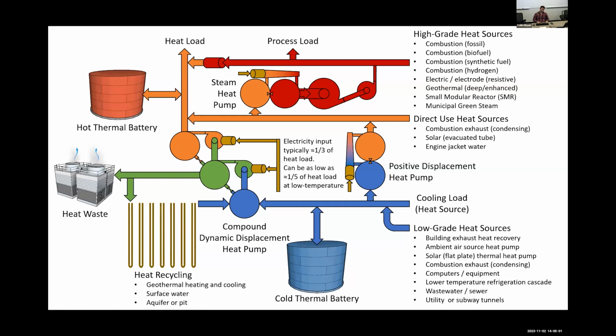And then there's other types of heat pumps on this diagram that we're not going to go into in detail, but there are opportunities to cascade into heat pumps that generate steam. But this is putting a lot more work in. You've already done the work to make heating hot water. It requires much more work to convert heating hot water to steam. So while it can be done, it's usually not the best choice. It's a lot more efficient if you can utilize heating hot water.